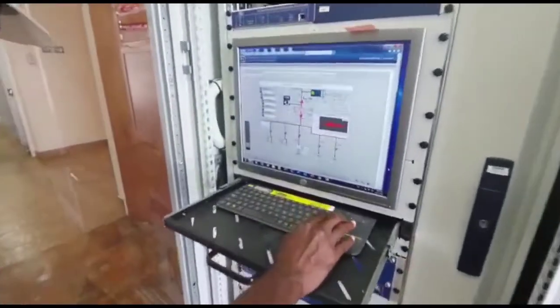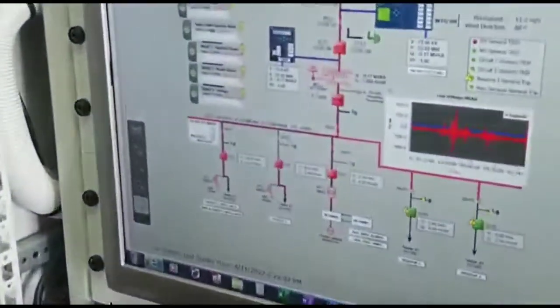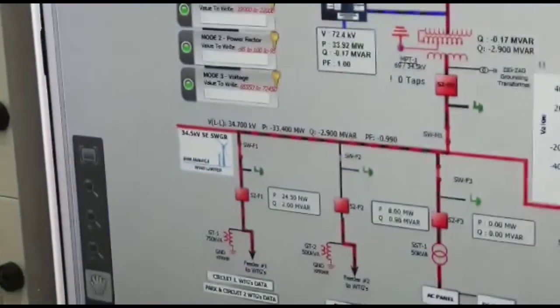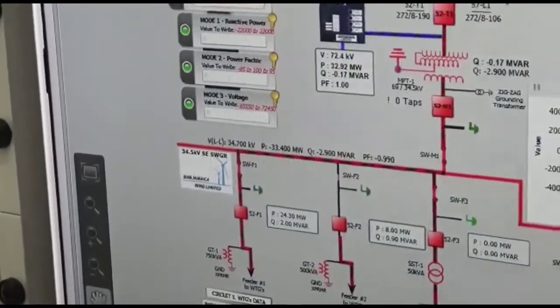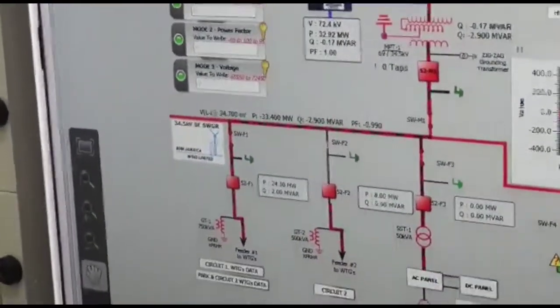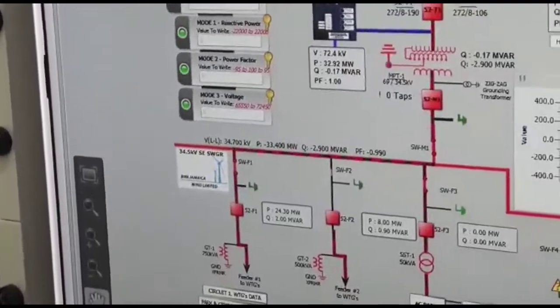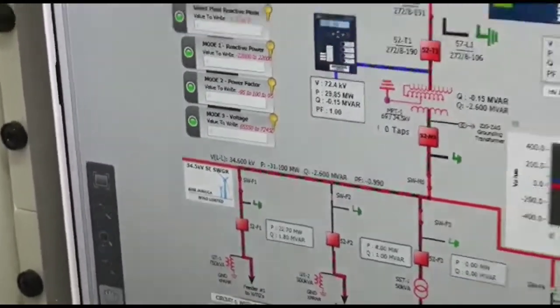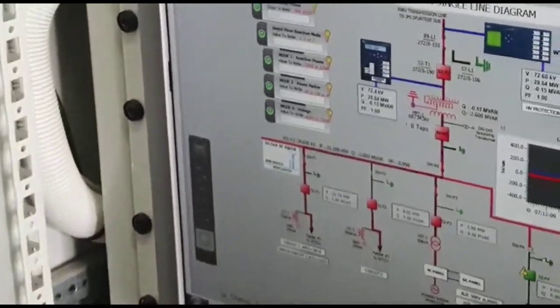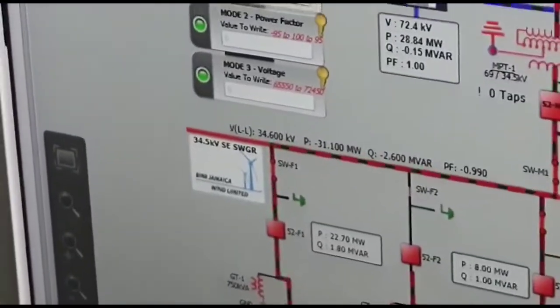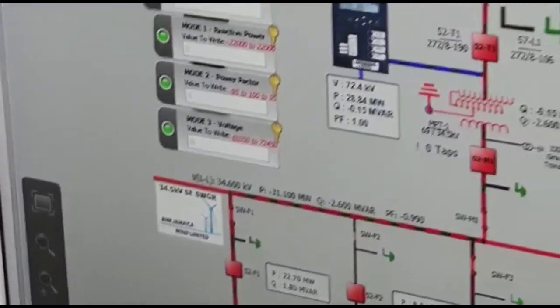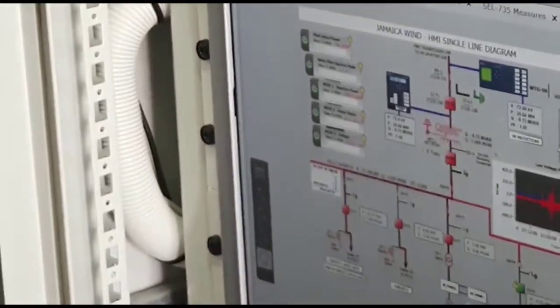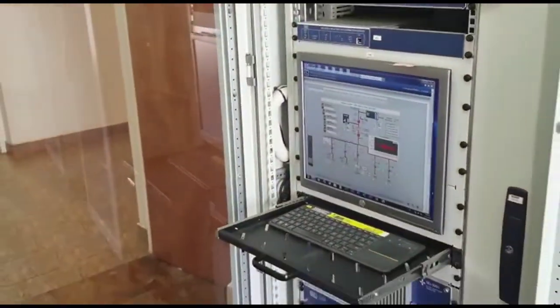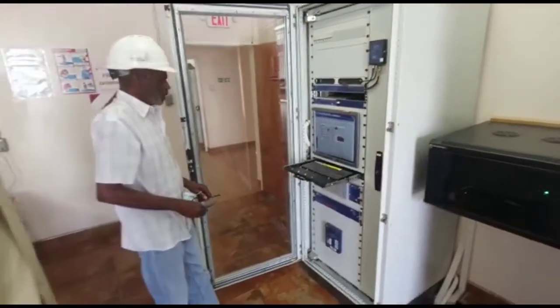Okay, it was at 34.9 when we were outside, and we're going to wait to see how low it will get. Oh, the voltage has moved from 34.9 down to 34.6 after we changed the setting on the tap changer, which means we moved down another 0.3 kV. Yes.